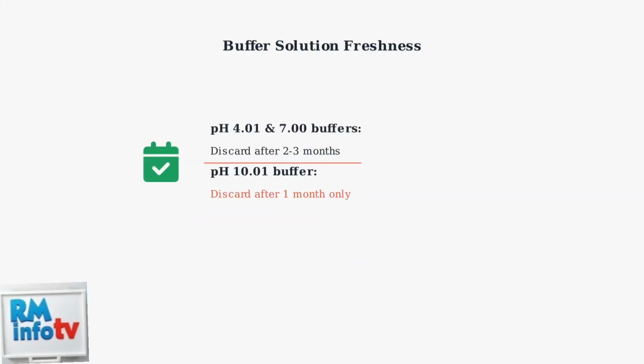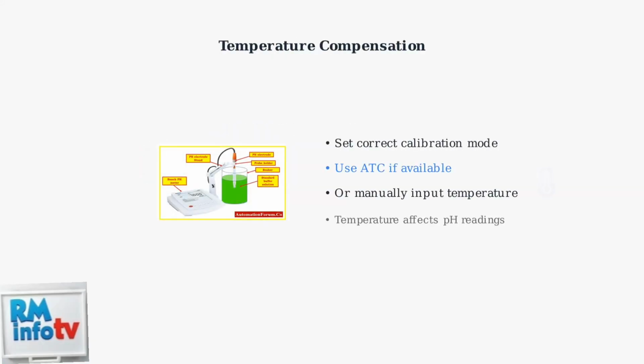Discard open buffers after 2 to 3 months, but pH 10.01 buffer should be discarded after just 1 month, as it degrades faster. Finally, ensure your meter is set to the correct calibration mode. If your meter lacks automatic temperature compensation, manually input the correct temperature for accurate results.